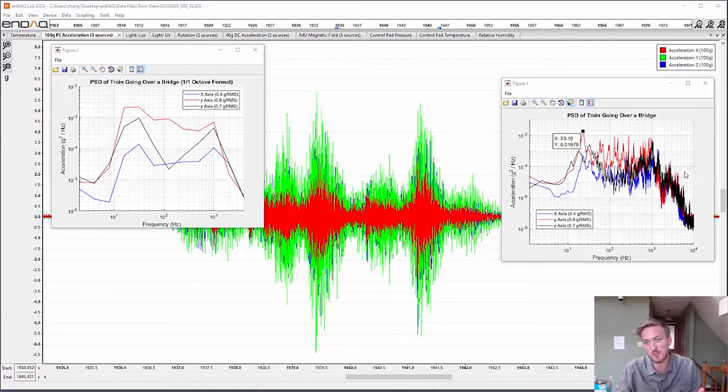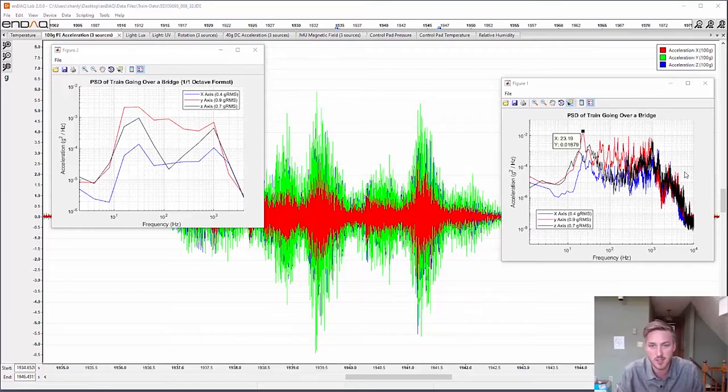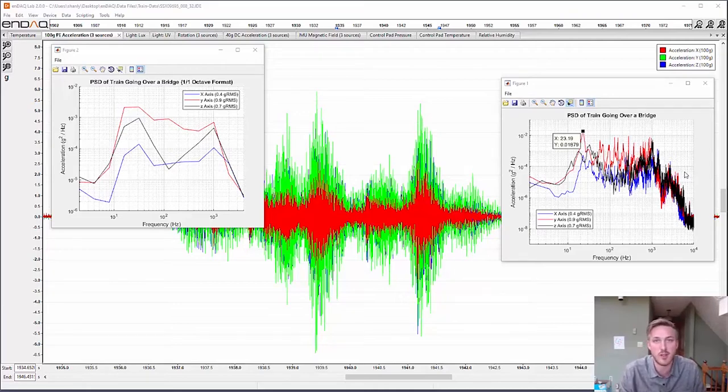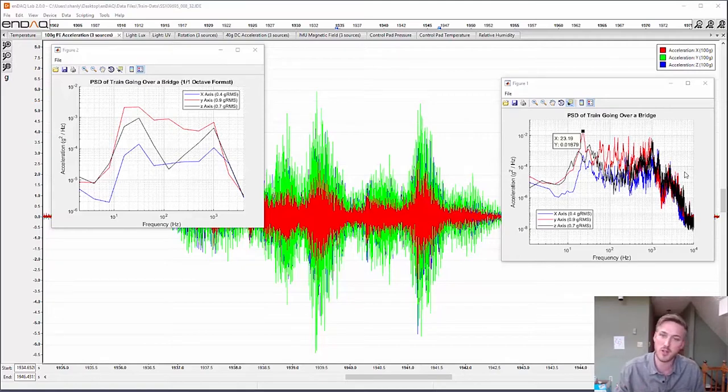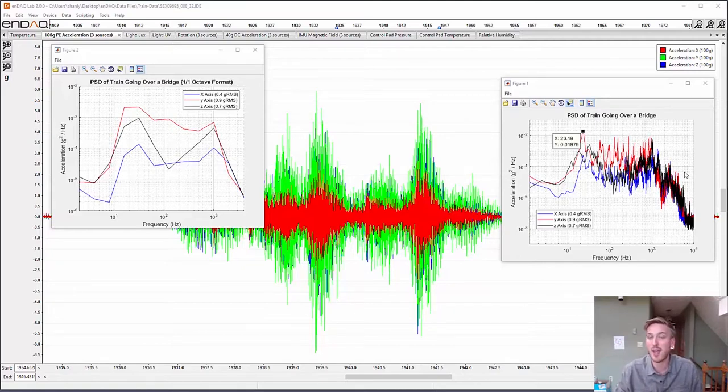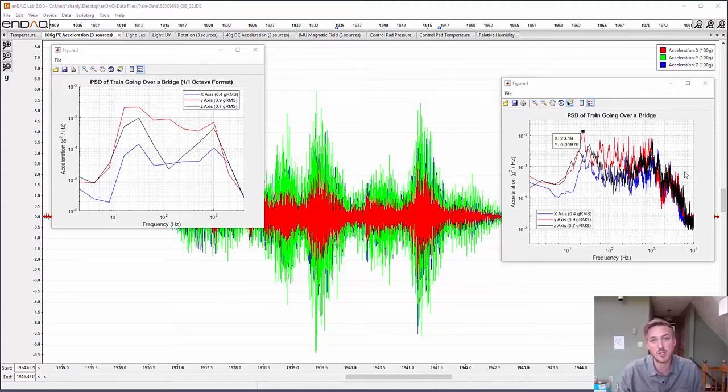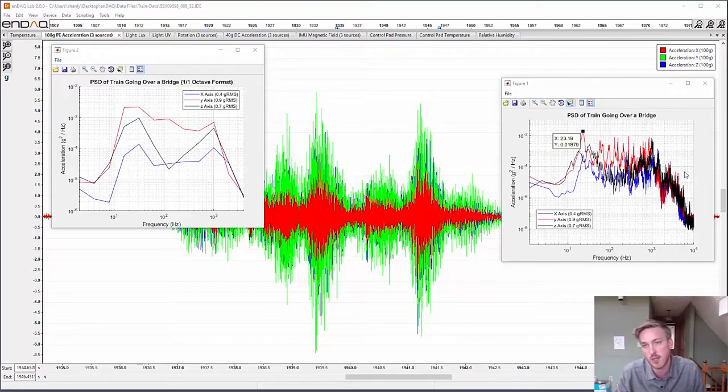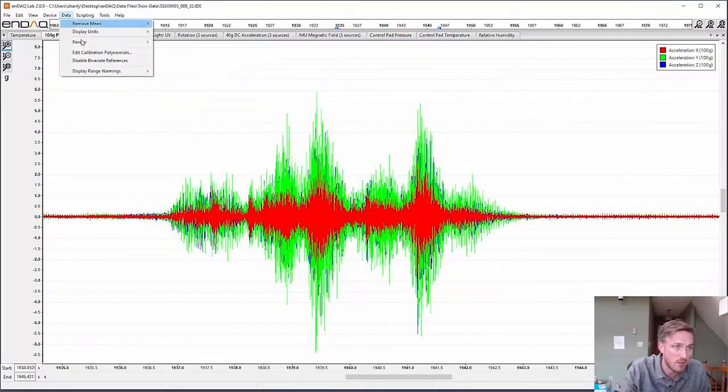What I was pleasantly surprised about was just how broadband that vibration is across really about from 20 Hertz all the way through a thousand Hertz. It's pretty steady but there's definitely a peak at 23 Hertz in the y-axis, which is going in the direction of the road. The energy, the acceleration amplitude measured by GRMS, is about 0.9 in the y-axis. So if you guessed 0.9 GRMS in the y-axis and a peak frequency of 23 Hertz, you were correct. So how do we get there?